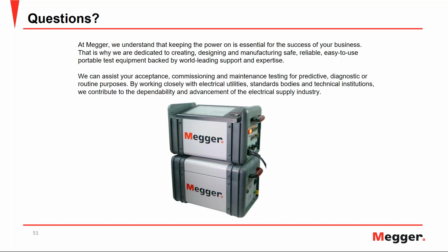So when we talk about negative power factor, usually you run into those typically on bushings, and the main reason why we see negative power factor is because of surface loss current. If the bushing surface has some contamination, some condensation because of high humidity, that would lead to some surface leakage current.